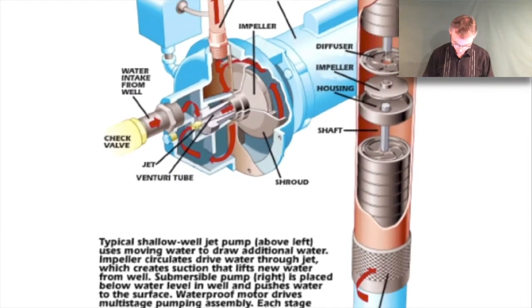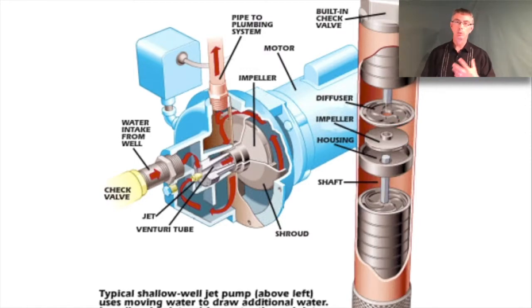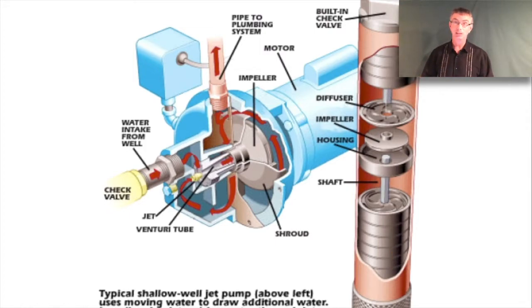On the shaft, the shaft rotates, and you see all of these - they're actually a housing, an impeller, and a diffuser. The housing here just houses the impeller. It's a closed impeller, and when the water comes out of the impeller it kind of swirls around from the outside. Then there's a little gap with the housing and it goes through this diffuser. The diffuser just helps reorient the flow so that it goes into the next impeller in the correct direction. You can actually see these are all stacked.